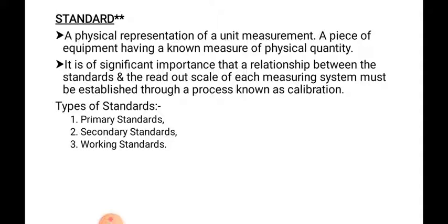Means what? We know that at our different technical laboratories, there are different instruments such as measuring instruments, and every instrument requires calibration. Calibration checks whether the instrument is working properly, or whether it is showing the reading within the prescribed or defined quantity. So every year each instrument must be calibrated by using the standard measures, or we may call them physical representatives.